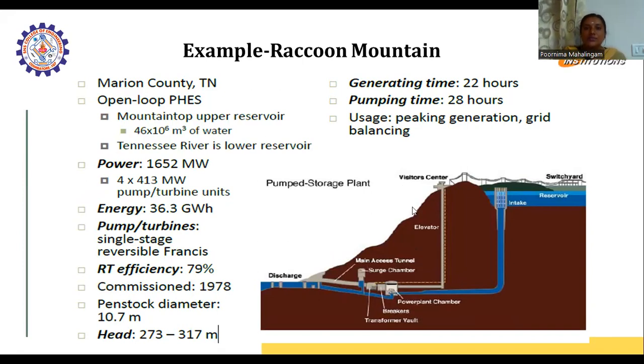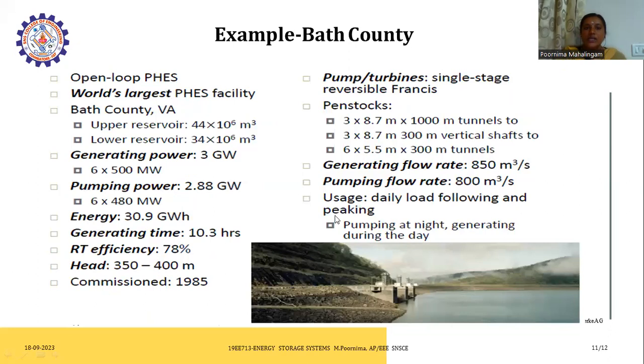Now let's see another example, the world's largest pumped hydro energy storage system. The upper reservoir contains 44 times 10 to the power 6 cubic meters, and the lower reservoir is 34 times 10 to the power 6 cubic meters. The generating power is 3 gigawatts, and the pumping power is 2.88 gigawatts. The energy is 30.9 gigawatt-hours, and the generating time is 10.3 hours. It has pumping turbines, a generator flow rate, and a pumping flow rate.